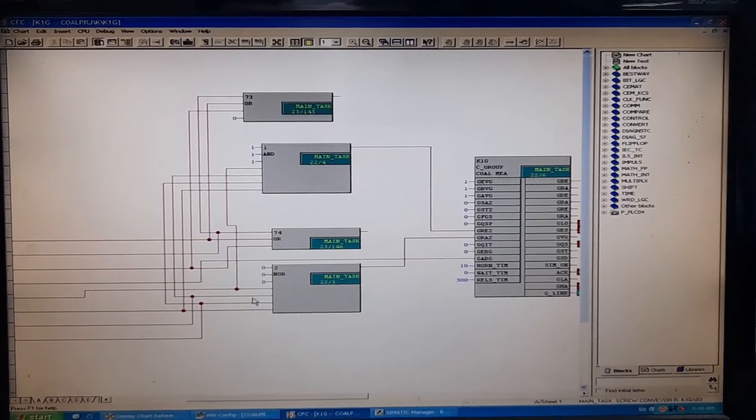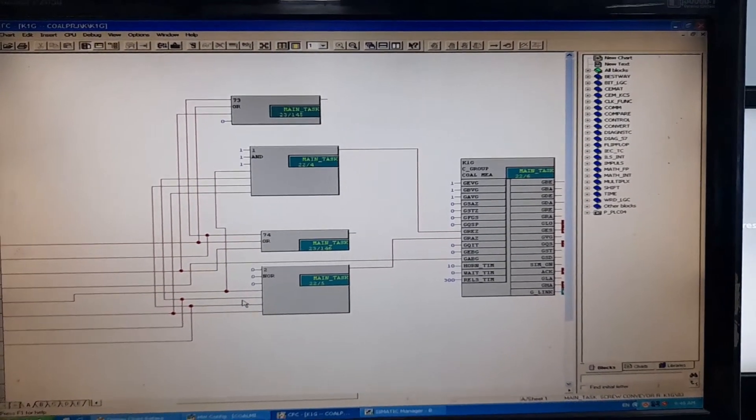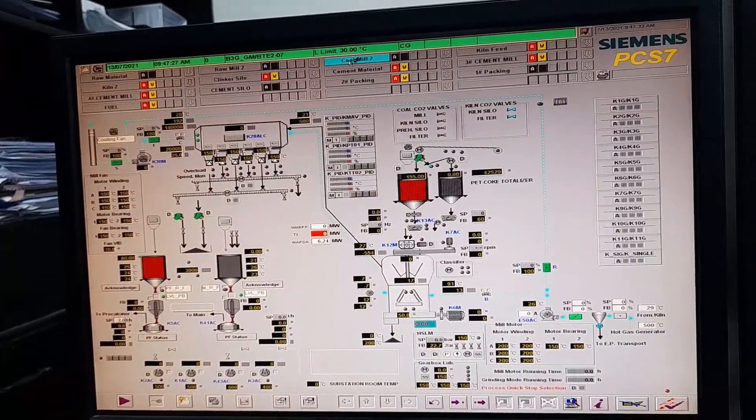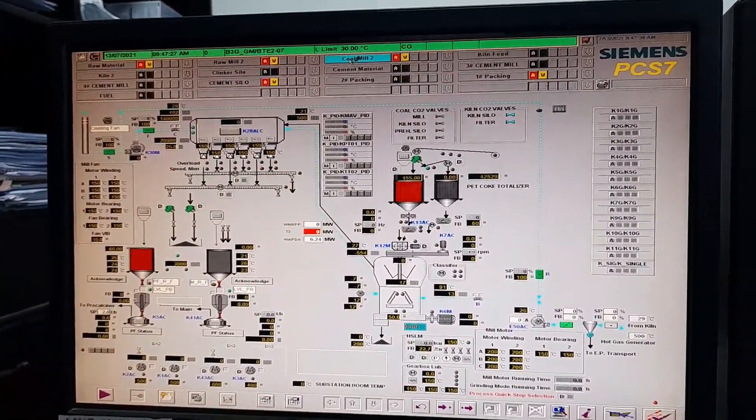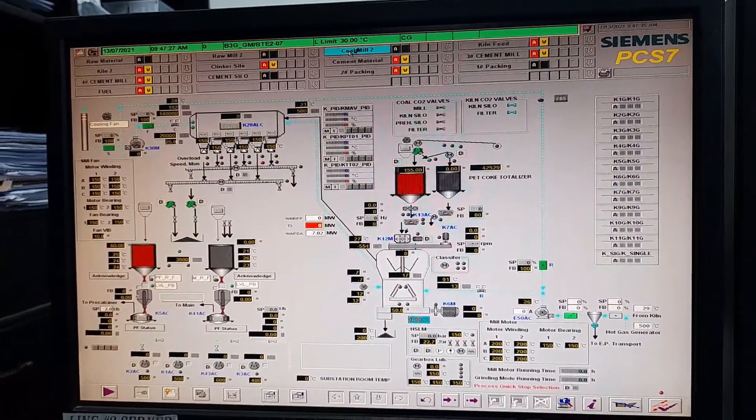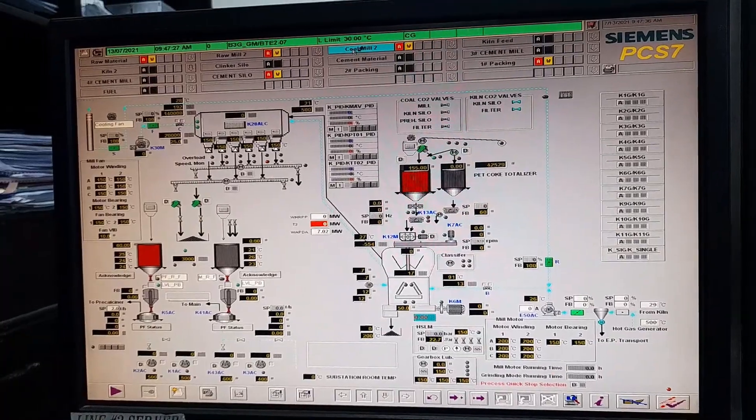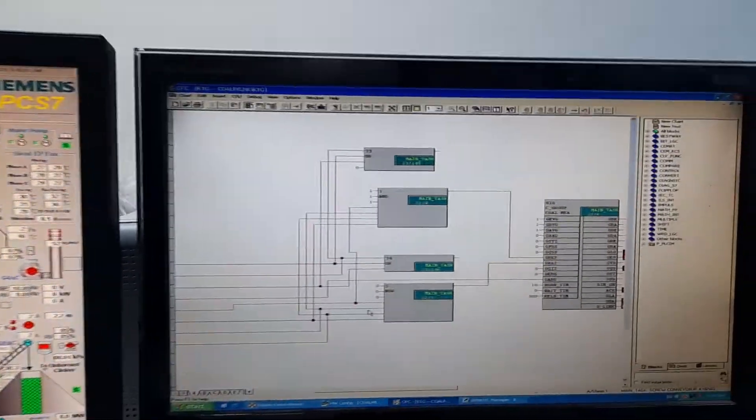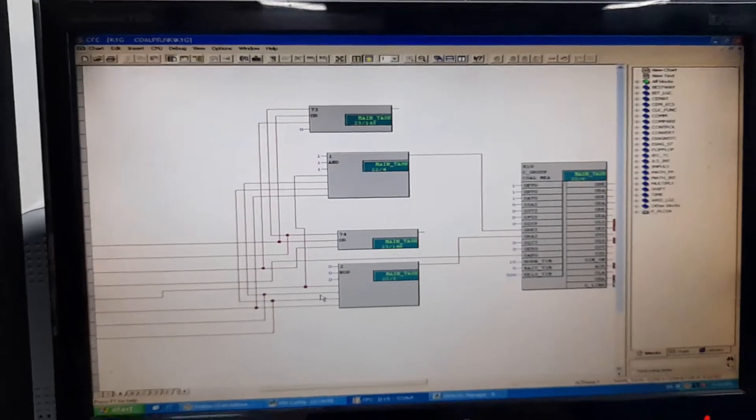I close this. If I look at the HMI of the coal mill, still it indicates that the PLC is in the stop mode. I will need to perform another download.